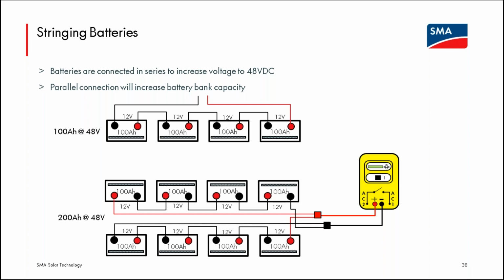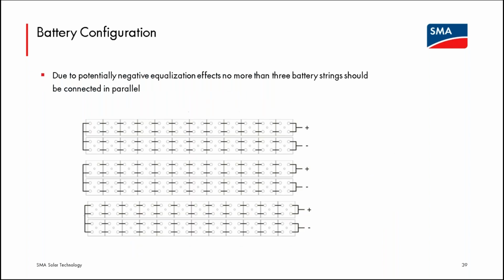So on the bottom part of the diagram, we're showing 2 strings that would be 100 amp hours at 48 volts. If they're wired in parallel, that's doubling the amp hour capacity. The Sunny Island treats that battery bank as a monolithic unit. It provides charge current, but it doesn't know where that goes. If there is a bad cell in one string, especially if there's limited charge current, if you don't have the unlimited current of a grid, the bad actor will begin hogging that charge current, and the strings will become unbalanced in state of charge.